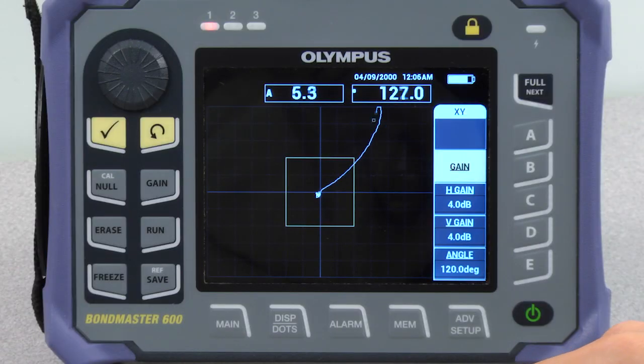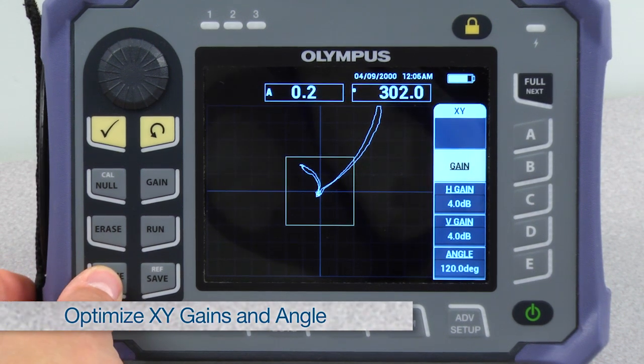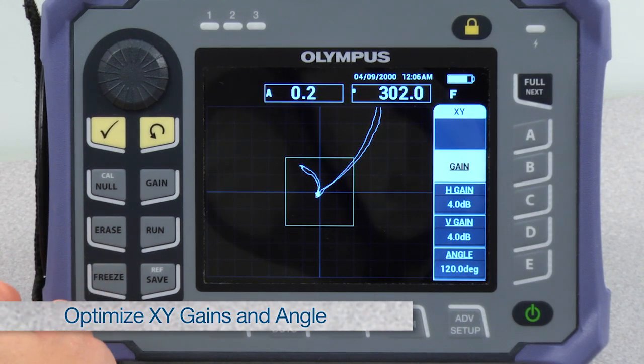If your reference standard has more than one disbond, scan all defects and optimize the XY gains and angle as needed.